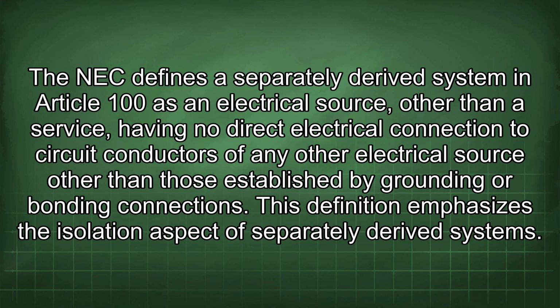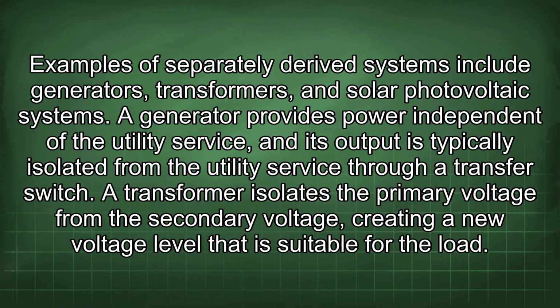The NEC defines a separately derived system in Article 100 as an electrical source other than a service, having no direct electrical connection to circuit conductors of any other electrical source other than those established by grounding or bonding connections. This definition emphasizes the isolation aspect of separately derived systems.